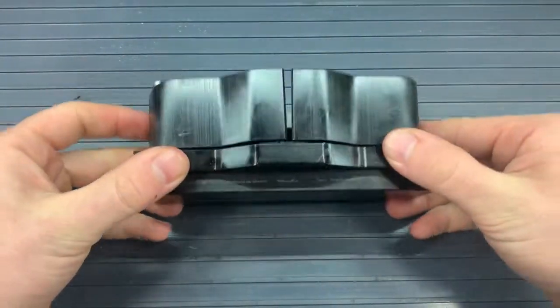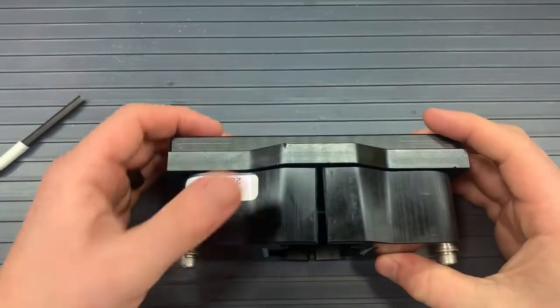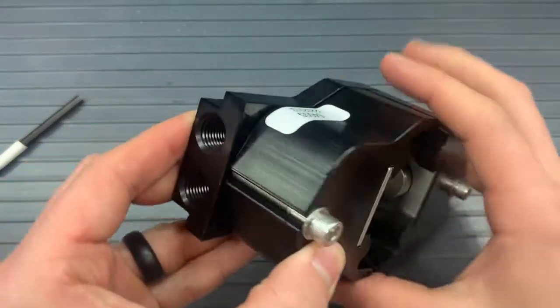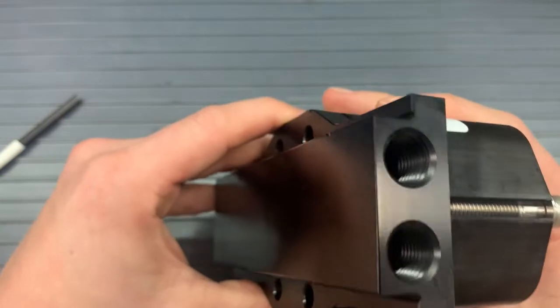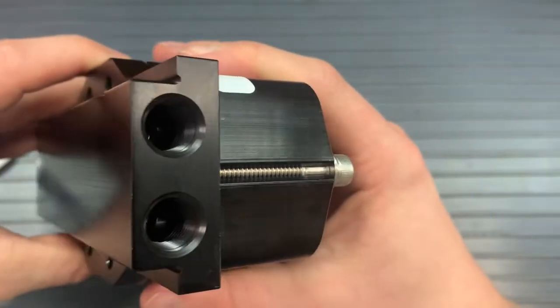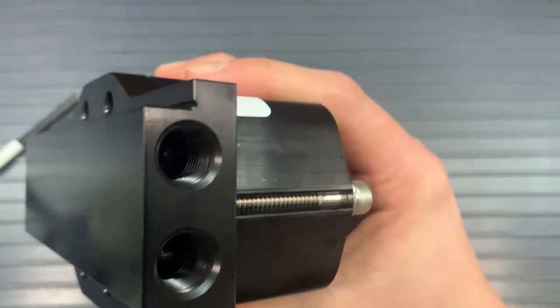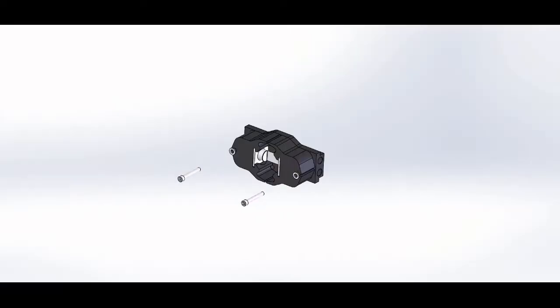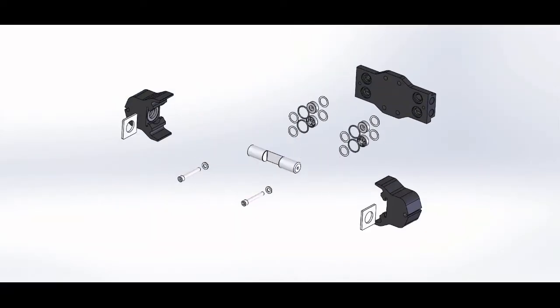Now that we have our pump all back together, let's double check that our valve is in the right spot. If you see that sticker, that port nearest it should be the outlet. If you look inside the pump, you may be able to see if you have an X facing you. If you do, you have done this correctly. This has been the tutorial on the 112T pump rebuild.